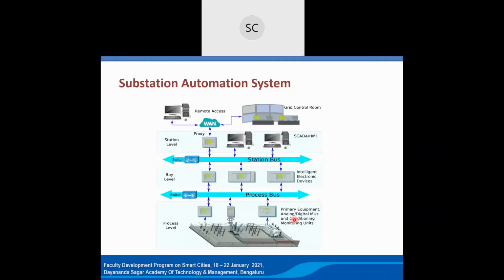Then it comes to the station bus. Here in the station bus, all these relays will be communicating on IEC 61850 communication protocols. Then it has to be connected to our main distribution control center - for example, if it is a statewide distribution control center, covering a complete utility, discom, or town-wise. But in many places, distribution automation is implemented city-wise or town-wise. For example, in Bangalore, we have a distribution automation system called DAS. Under R-APDRP, more than 78 towns have implemented town distribution automation systems, like in Hyderabad, where CPRI was the consultant for the Andhra Pradesh and Telangana utilities.